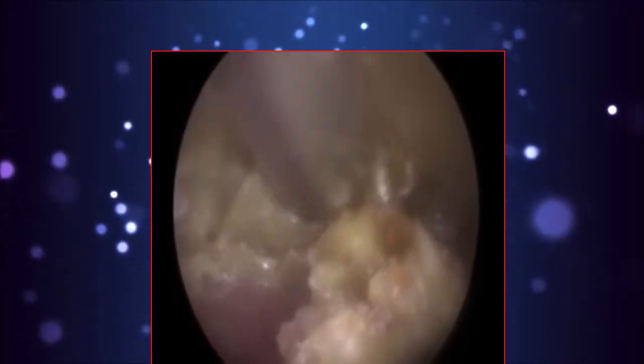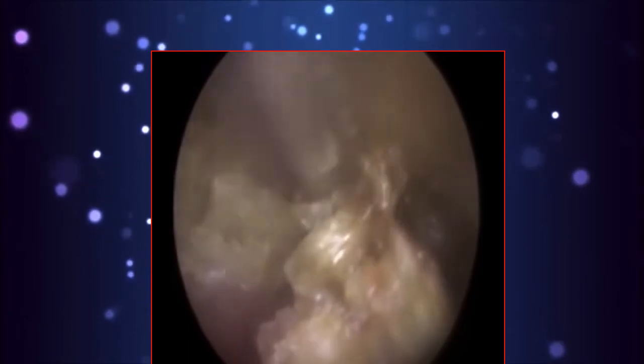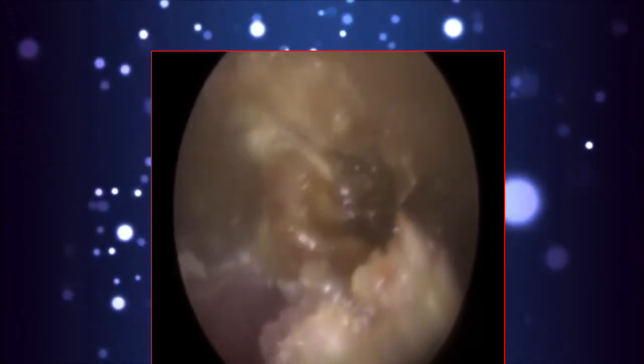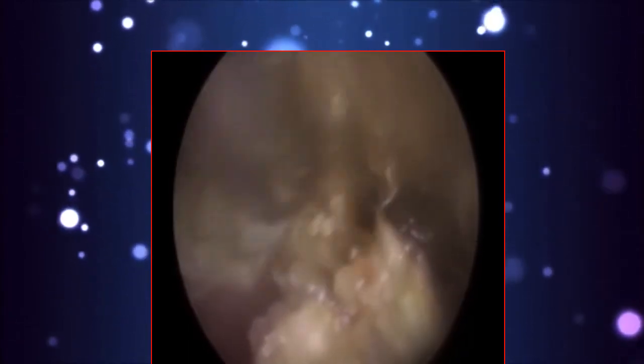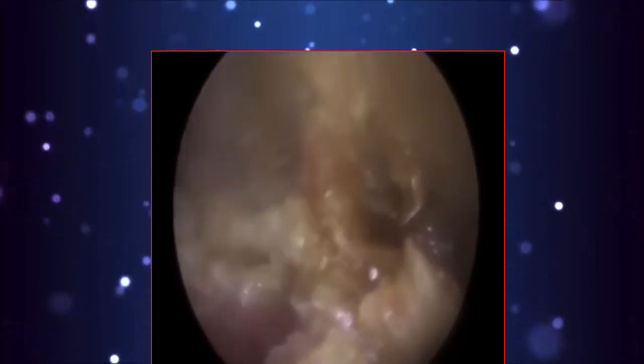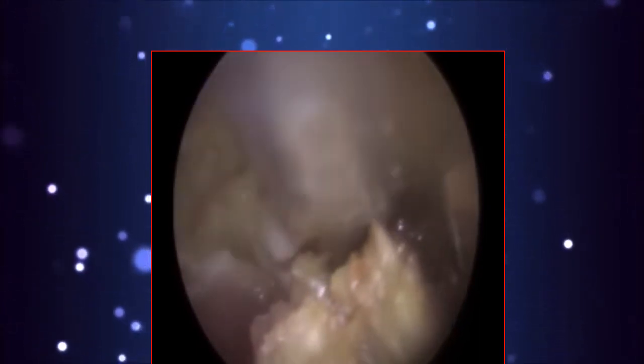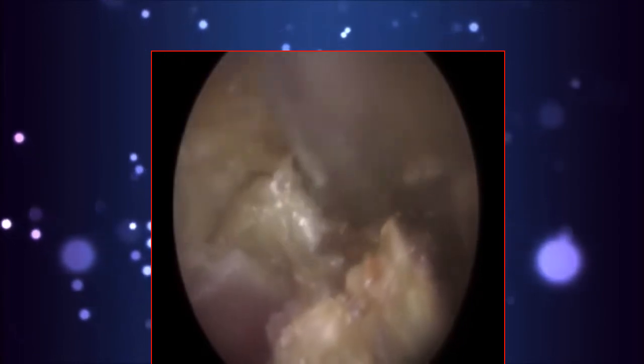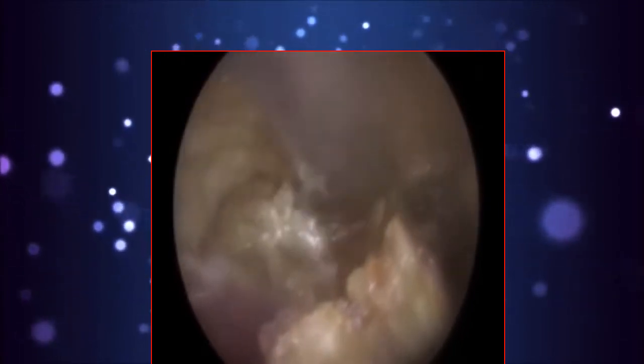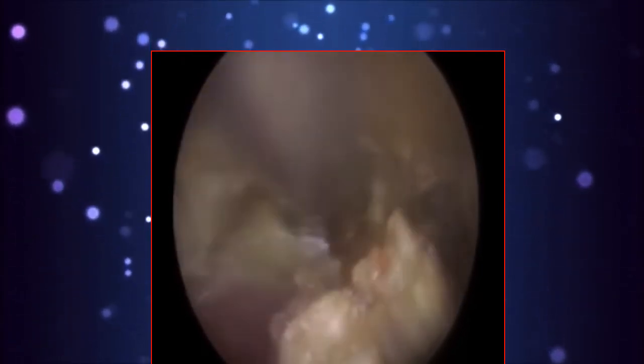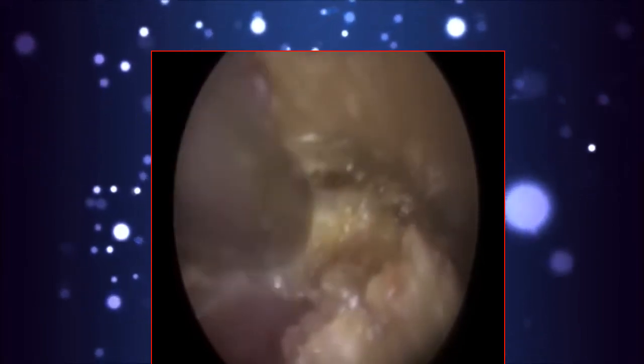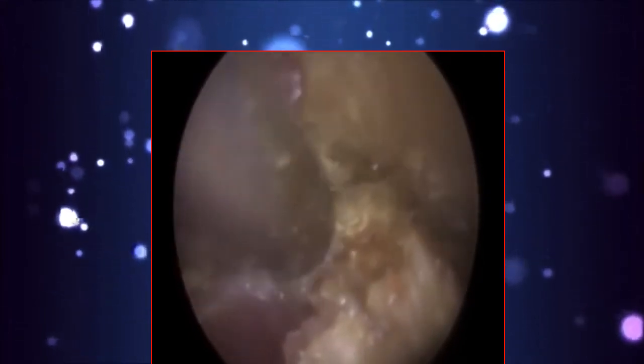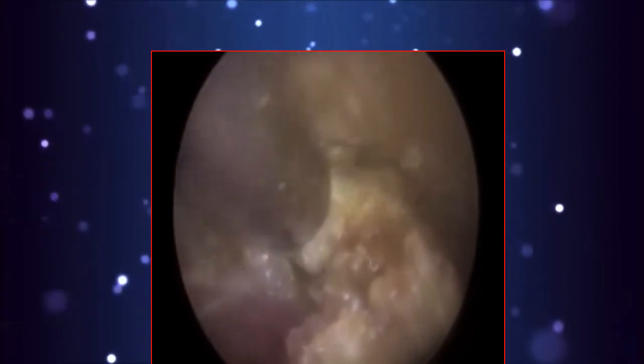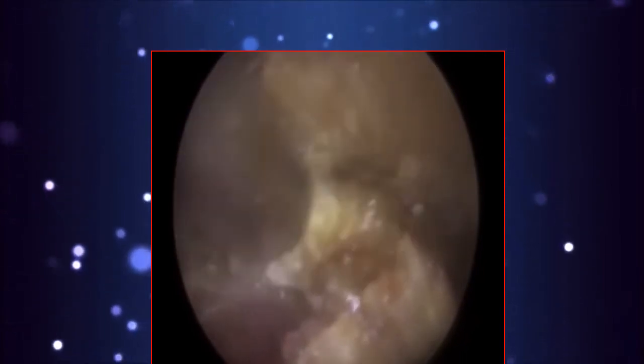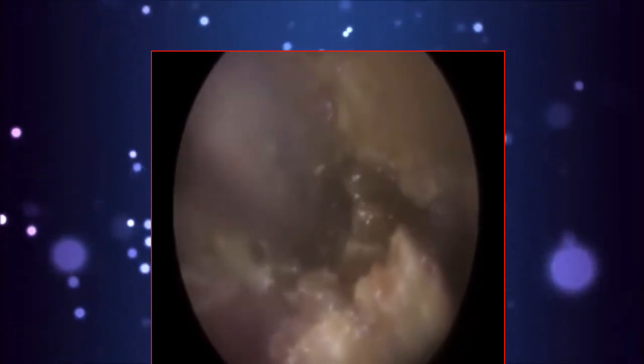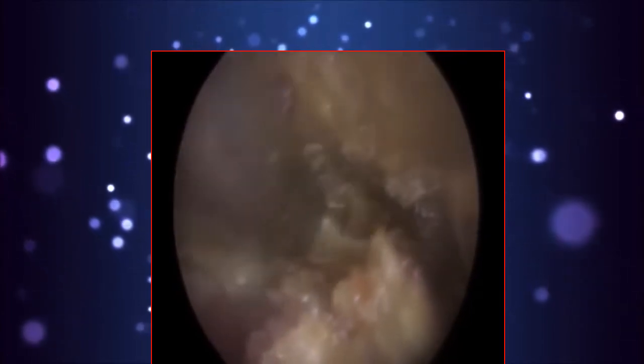Just trying to bring it a bit forwards, and as I do, I will then alternate between the range of ENT micro instruments. The most common is the suction probe, which is what I'm using at the moment, and this is the Zollner suction probe. We do have a fine end attachment that we can add to the top. The fine end is less suction power, but it's less noisy, so it's less traumatic for the patient if we come in contact with the canal wall or eardrum. We generally use the fine end for deeper wax and wax that's impacted on the eardrum.